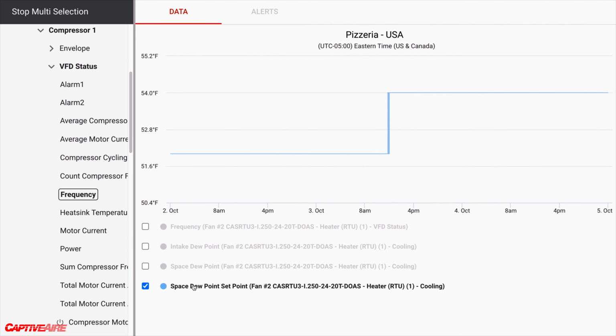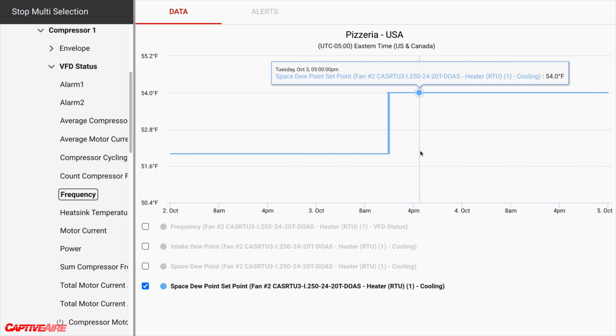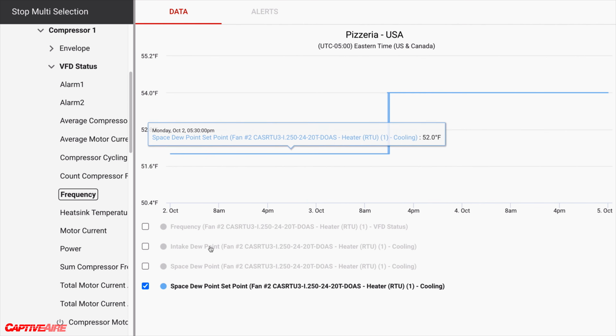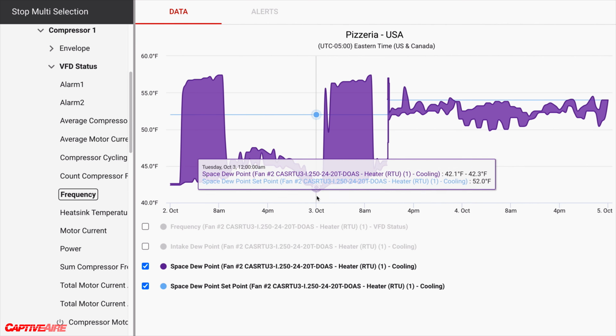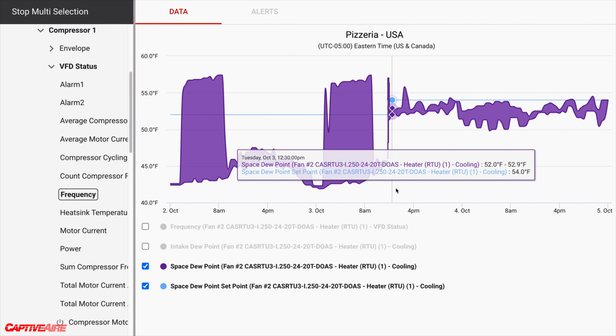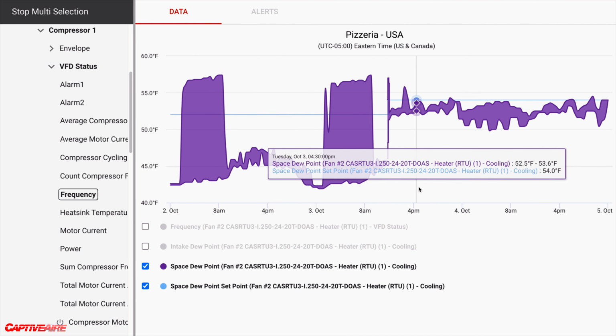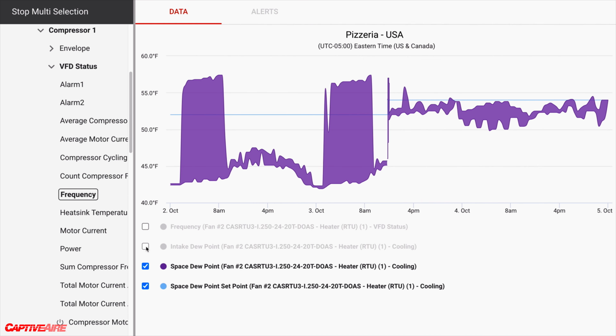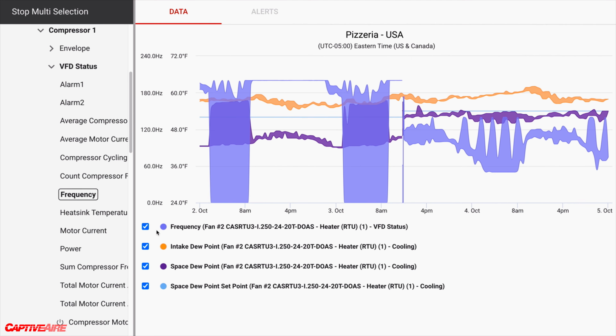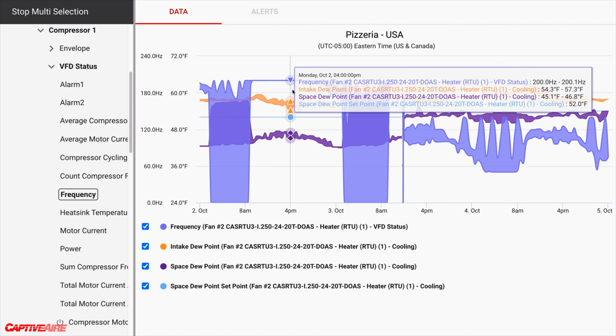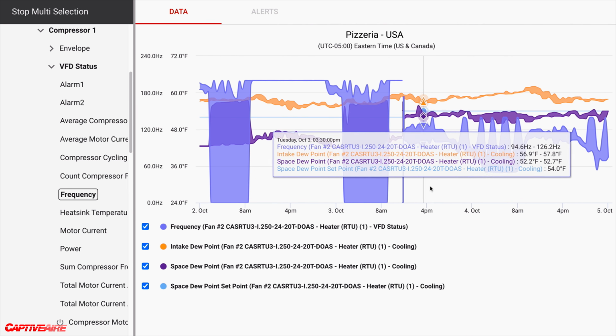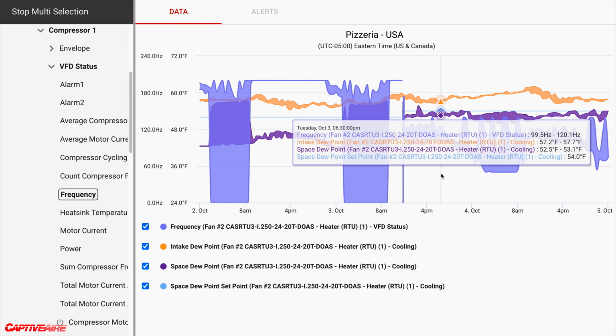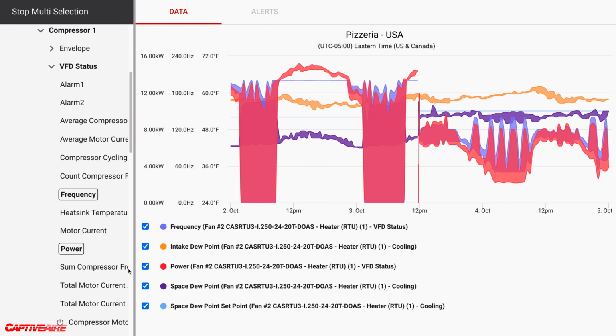So, another spot for some savings, they bumped that set point up from 52 to 54, but you can also see a drastic change in the actual space dew point going from the 40s back up into that 52 to 54 range. This is a really good improvement, where that purple line went from below the set point up to the actual set point of the space. And then we can see that compressor speed went from very high speeds down to much lower speeds. That translates to the comfort still being there, but we're spending a lot less energy to maintain that comfort of the space.